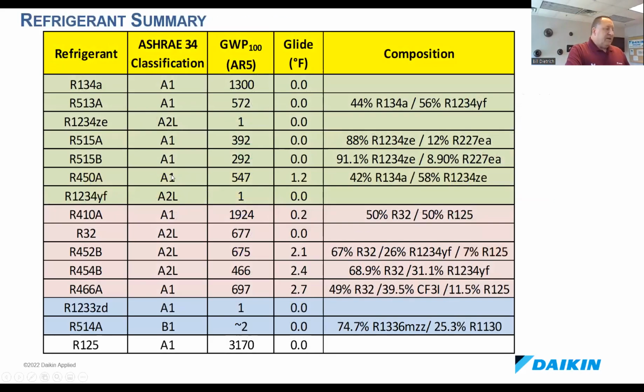So what I put together here for you is just a summary. The green ones are kind of the 134a likes. So you get a classification of ASHRAE, what its GWP is, and if it's a blend, what it's made up of. And then I've also got another column here called the temperature glide. And what you'll see is some of these refrigerants have a number like this with a small a on it, 1, 2, 3, 4. And then you have some numbers with a capital letter.